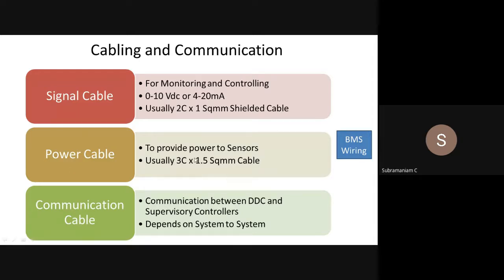The power cable, in case you want to give UPS power to the controller, because you don't want the system to be down in case of a power failure or a transition from normal power to DG power. Then we have to use power cabling and things like that, and a communication cable, because you will be having a lot of DDC controllers. So one should communicate to the other, or they all should communicate to a network switch, because we are talking about these controllers on an IP based network, so that they will have an IP address. So that communication cable is there.